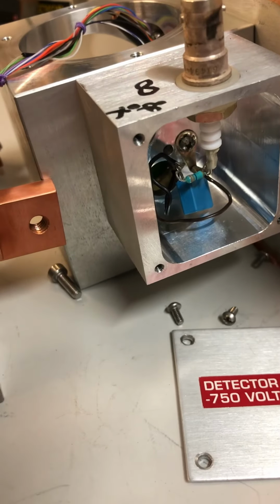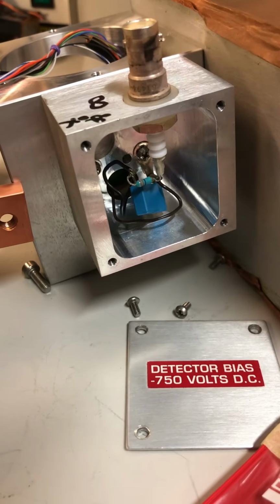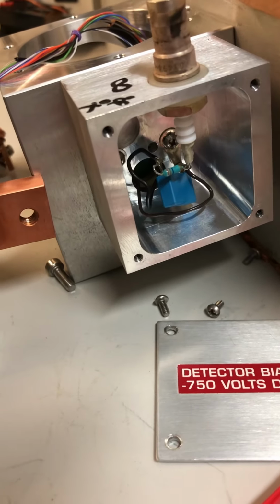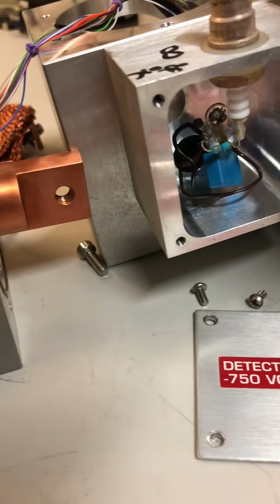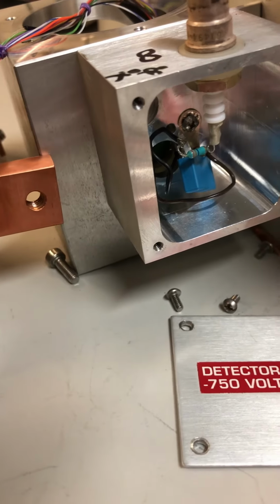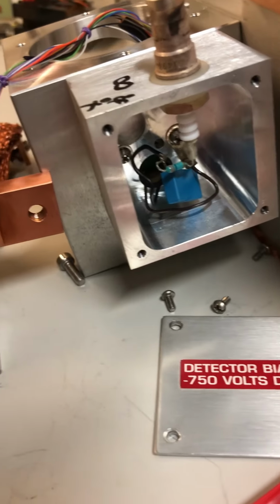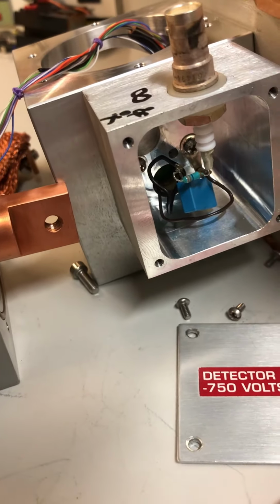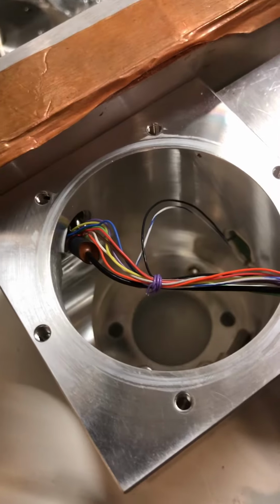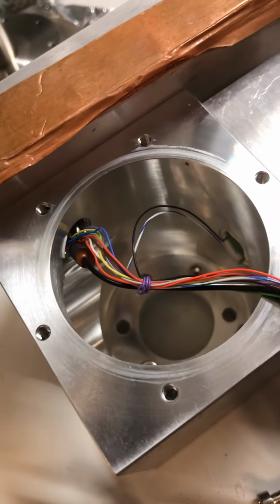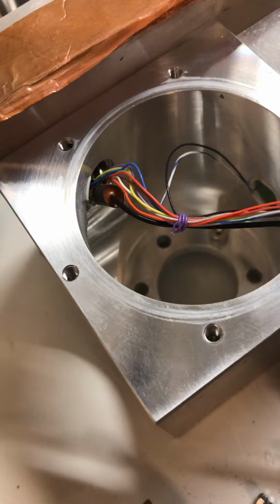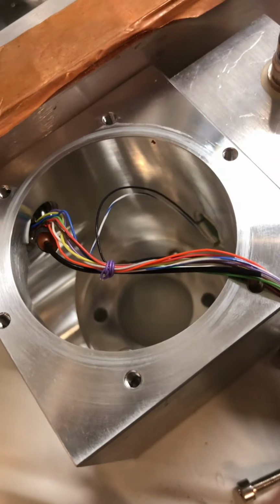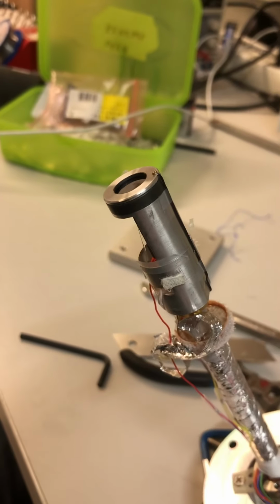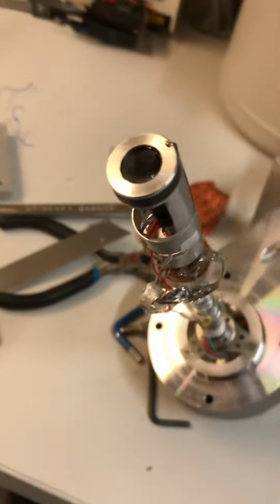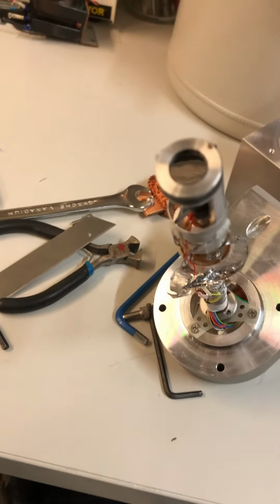Inside the bias box, minus 750 volts goes to one wire through a large resistor and capacitor filter, and the other one goes to ground. High voltage goes to the black wire, and the white with blue, it is actually ground. Detector, we see that negative high voltage goes to the detector front surface.